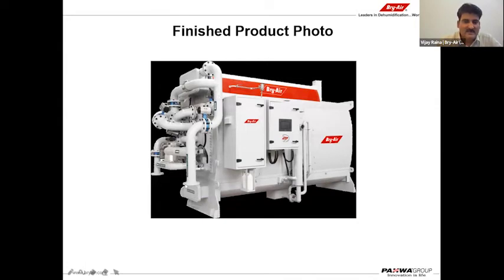This header is a cooling water and hot water changeover, which is happening every 7 minutes in this technology. In order to get a continuous chilled water temperature at the bottom of the chiller, we use this cyclic time through HMI, and there is a changeover through 10 to 12 butterfly valves. These butterfly valves are pneumatically activated, and they give the direction for cooling water changeover and hot water changeover between the chambers.